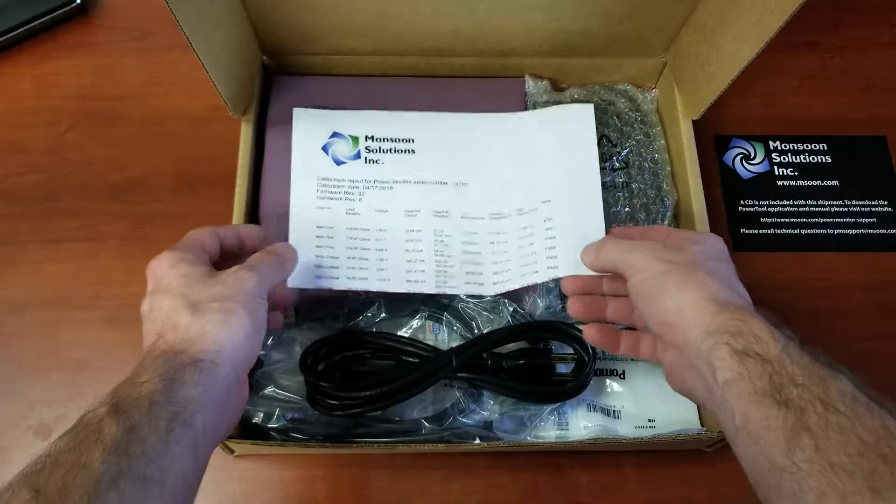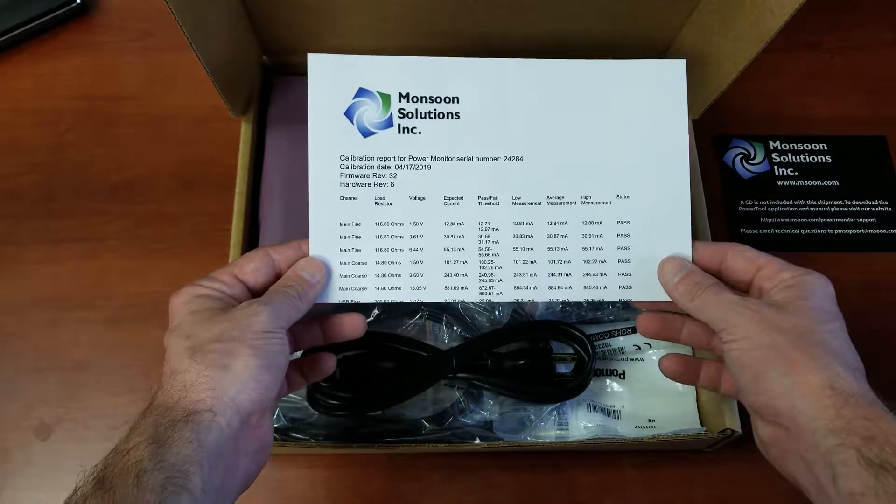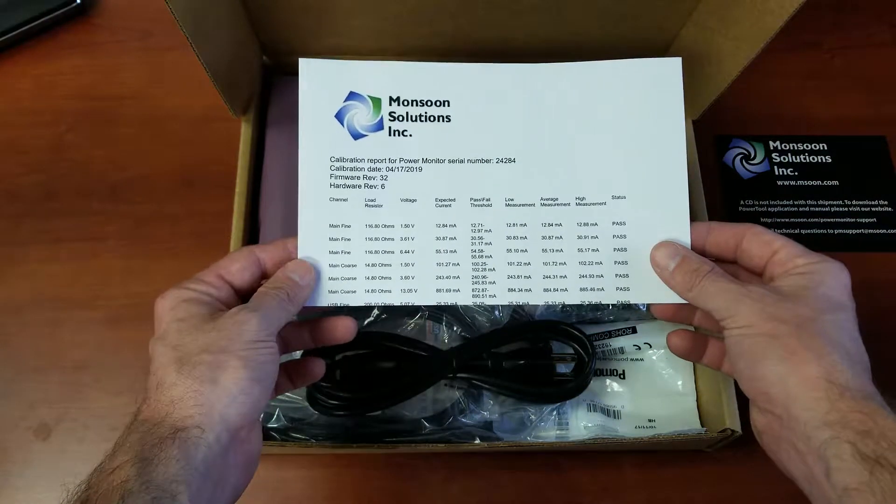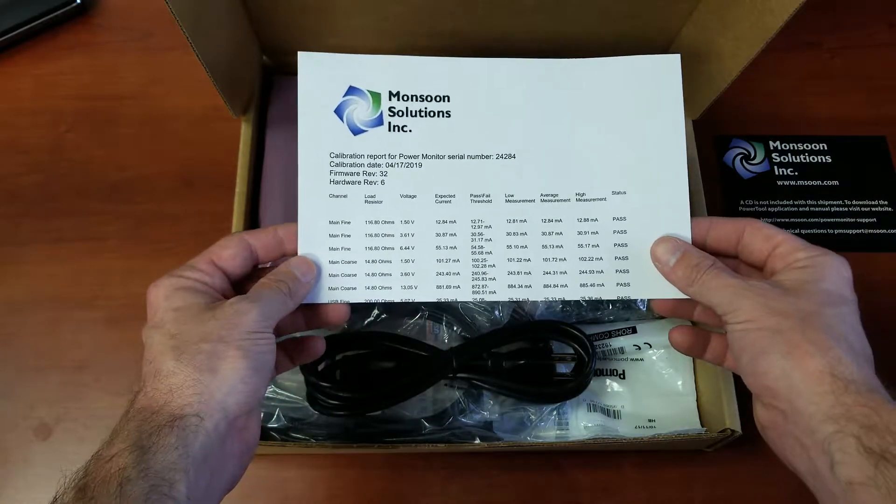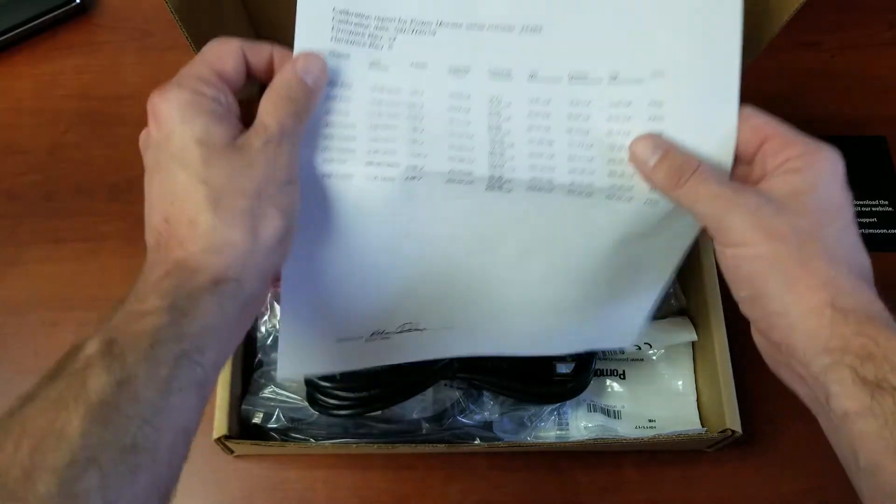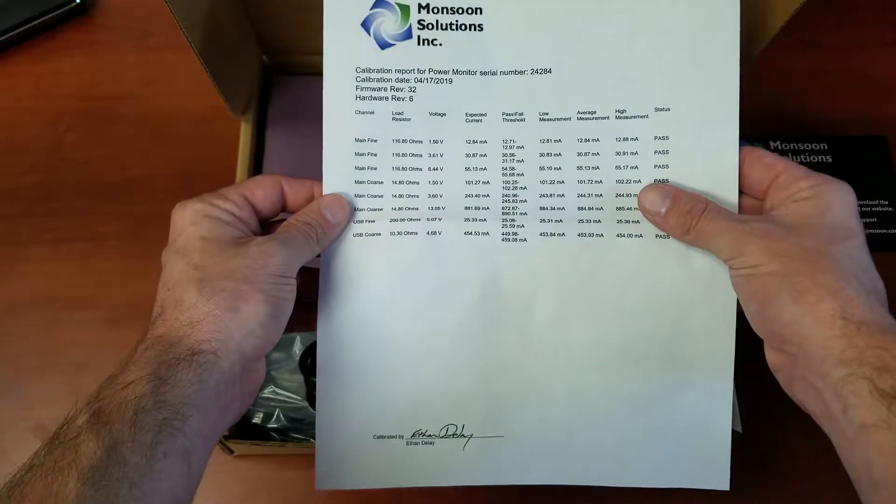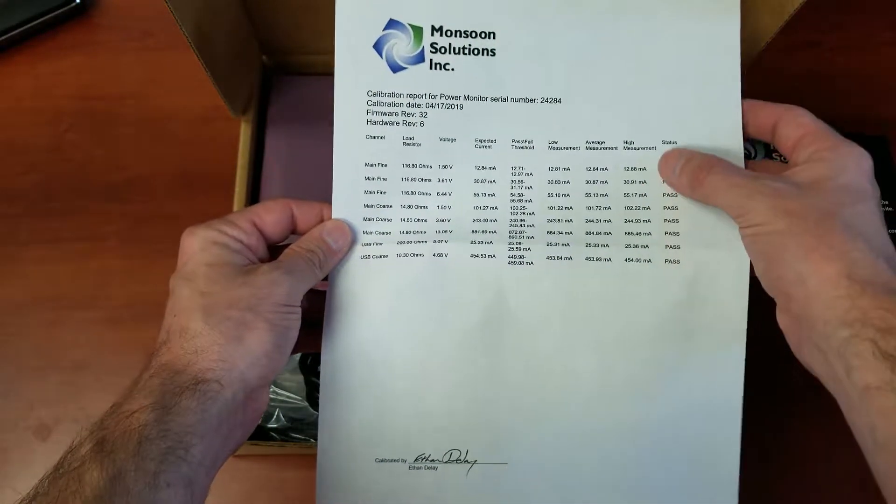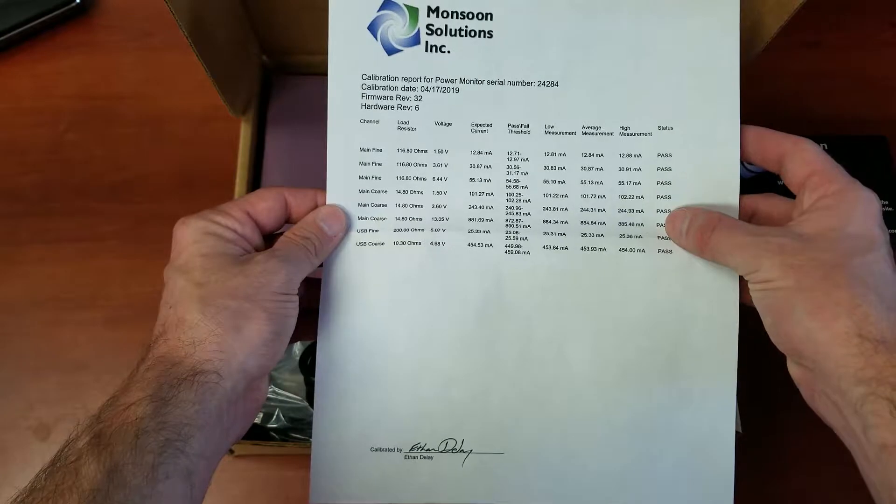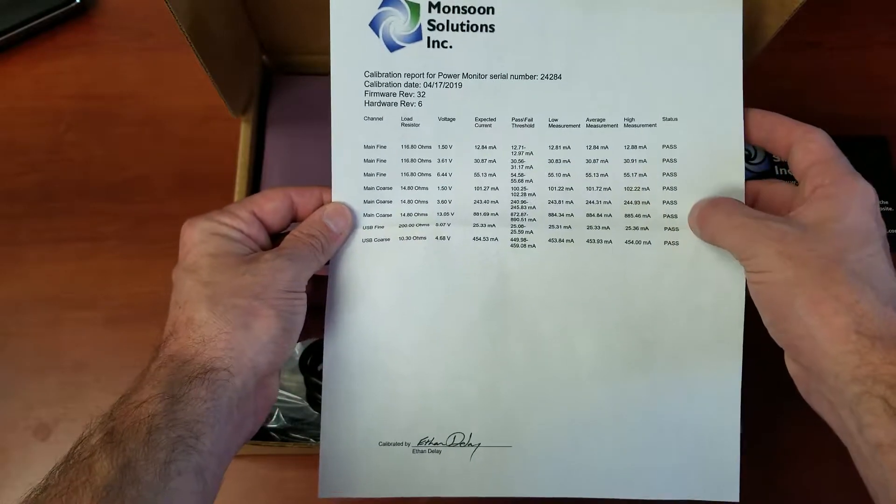Next thing is this piece of paper right here. This is a calibration report which is included with every high voltage power monitor. It is signed by the technician who calibrated the device and has the details of the different channels and what the calibration results were.